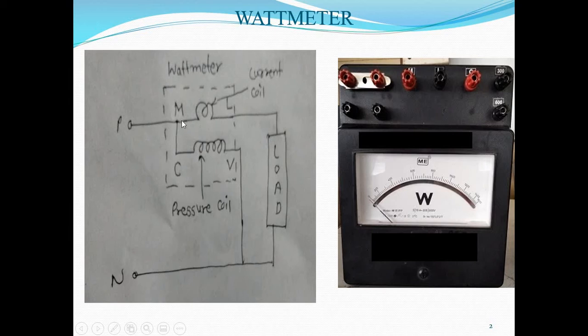The first terminal is M, that is the main terminal. The second one is L, that means the load terminal. The third one is C, that is the common terminal. And the fourth one is V, that is the voltage terminal. In the watt meter, there are two coils: the first one is the current coil, which is connected between M and L, and the second one is the pressure coil, also called the voltage coil, which is connected between C and V.